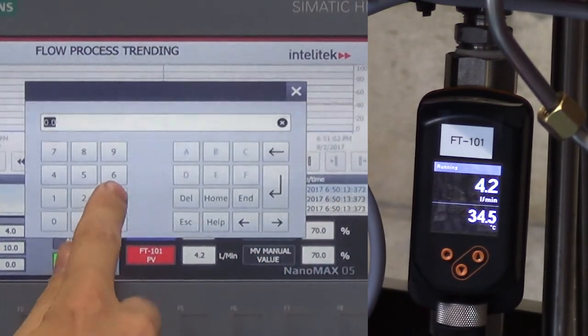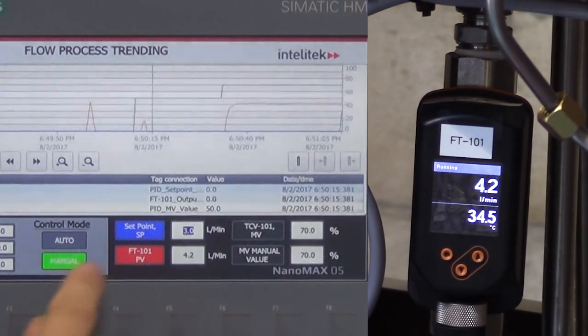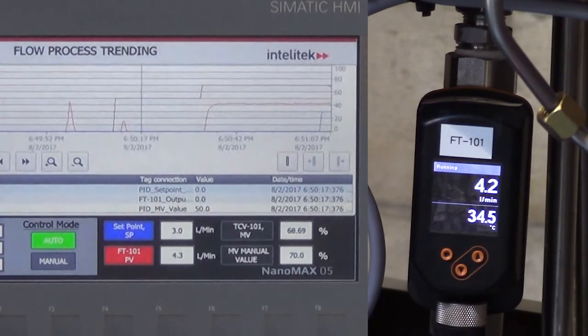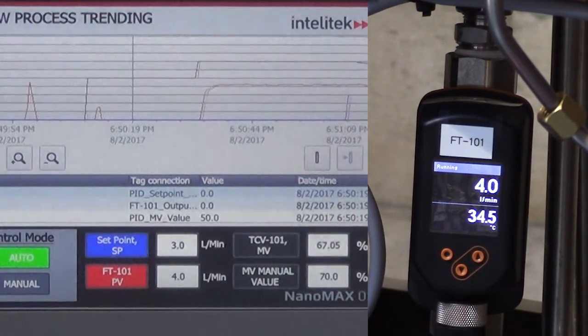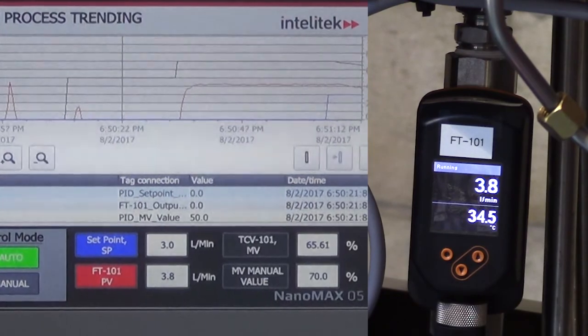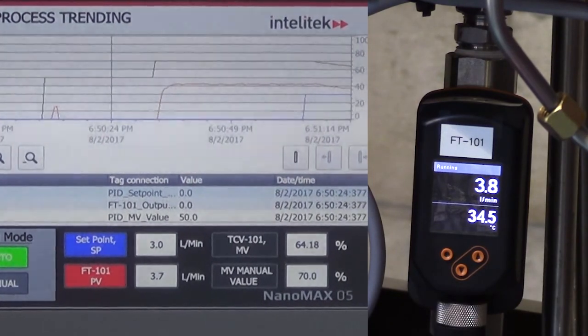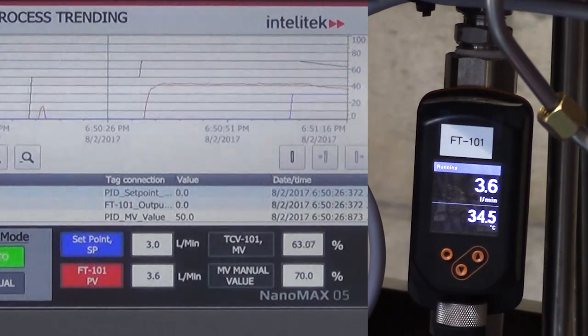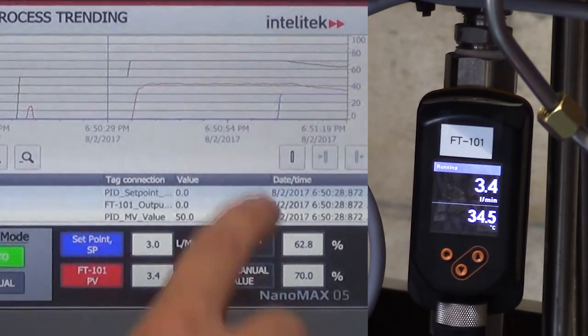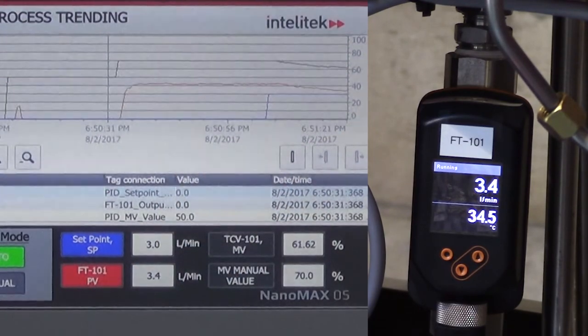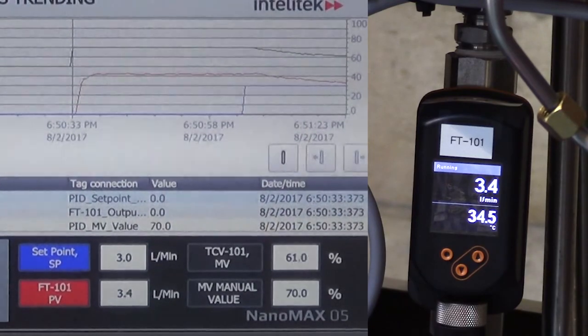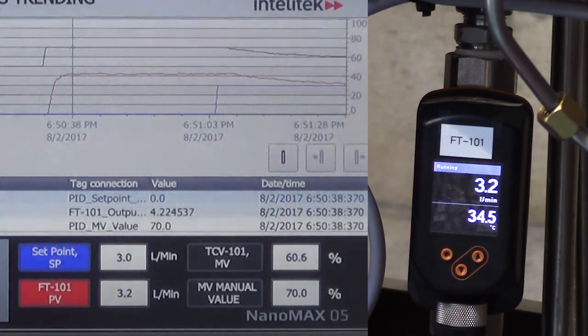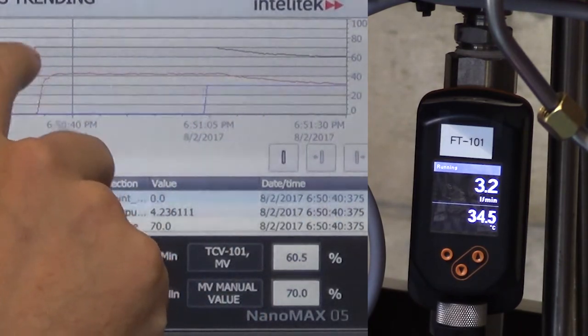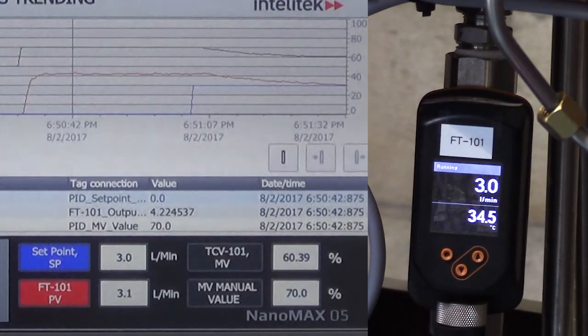And a preset set point, say I want it to be 3, I can enter automatic mode and the control system will automatically react to what it's currently sensing and then adjust the flow rate to what our target is. And again, we can see the blue line representing our set point, a red line representing our sensor's measured value, which is our flow meter, and we can see our valve's value as well.